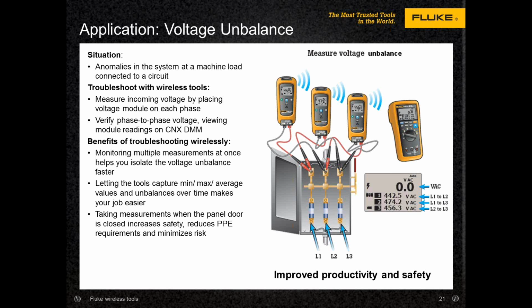Now, what about the category rating for electrical safety on these? All of our products, like the voltage modules and the meter, are category 4, 600 volts, category 3, 1,000 volts in most cases. So they've got the highest safety ratings that we use in most of our products. So good for working indoors from the service entrance onward, and category 4, 600 volts also allows you to measure utility power or line power outside, like at the meter. Up to what voltage on these? Up to 600 volts. It depends on whether you're indoors or outdoors.